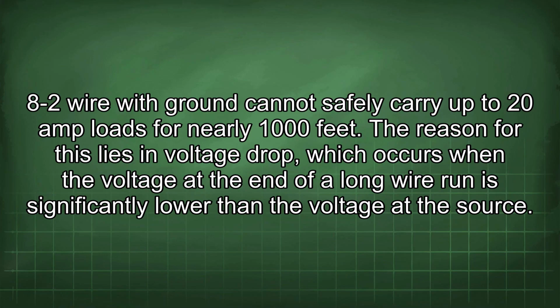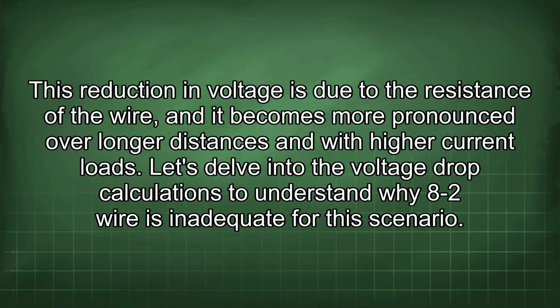8-2 wire with ground cannot safely carry up to 20 amp loads for nearly 1000 feet. The reason for this lies in voltage drop, which occurs when the voltage at the end of a long wire run is significantly lower than the voltage at the source. This reduction in voltage is due to the resistance of the wire, and it becomes more pronounced over longer distances and with higher current loads. Let's delve into the voltage drop calculations to understand why 8-2 wire is inadequate for this scenario.